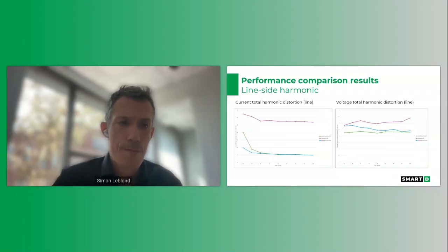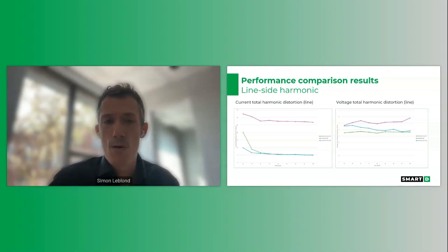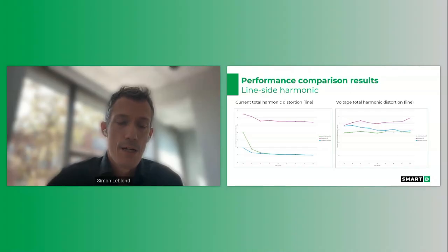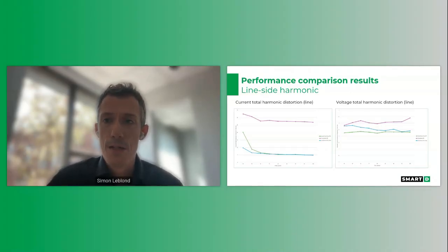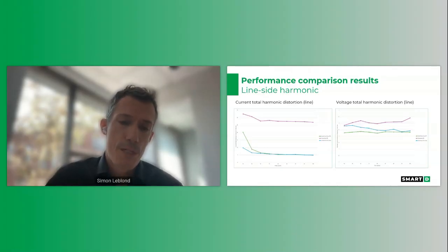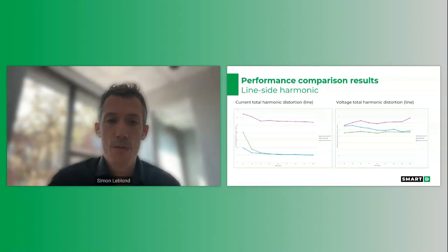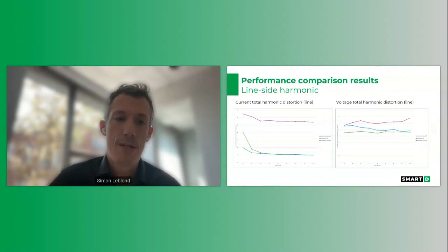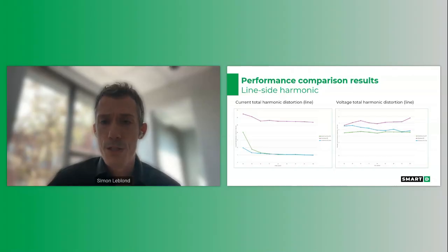And finally, to conclude our test results, we can see that the harmonic situation on the line side is quite similar between the passive filter and the Clean Power VFD, versus the standard or conventional VFD that has around 30% harmonics on the line side. And so with both the SmartD VFD and the passive harmonic filter, we're meeting IEEE 519 standards, maintaining harmonics below 5%, even in a very stiff grid environment. And same thing for the voltage total harmonic distortion, where we can see that the Clean Power VFD actually even outperforms the passive filter performance.